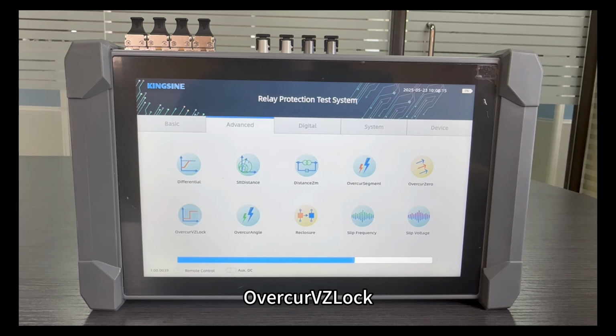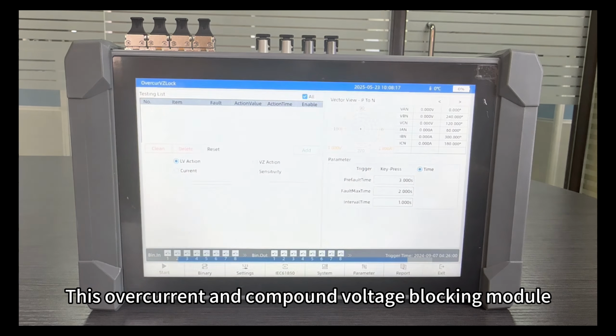Overcurrent VZ Lock. This overcurrent and compound voltage blocking module resolves conflicts where fault currents fail to meet quick break settings during phase or three-phase short circuits. It introduces a composite voltage loop to reduce overcurrent thresholds. Tests include undervoltage or negative sequence voltage action values, current thresholds, and maximum sensitivity angles.